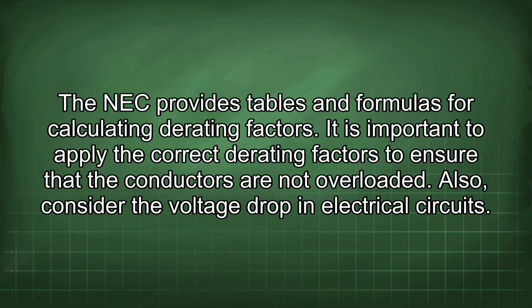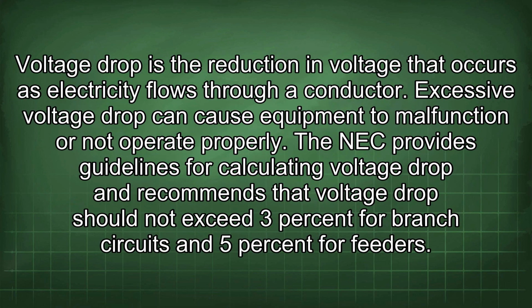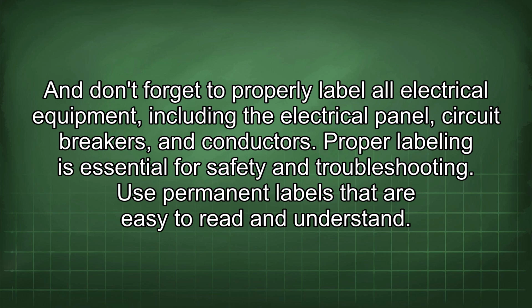Also, consider the voltage drop in electrical circuits. Voltage drop is the reduction in voltage that occurs as electricity flows through a conductor. Excessive voltage drop can cause equipment to malfunction or not operate properly. The NEC provides guidelines for calculating voltage drop and recommends that voltage drop should not exceed 3% for branch circuits and 5% for feeders. And don't forget to properly label all electrical equipment, including the electrical panel, circuit breakers, and conductors.